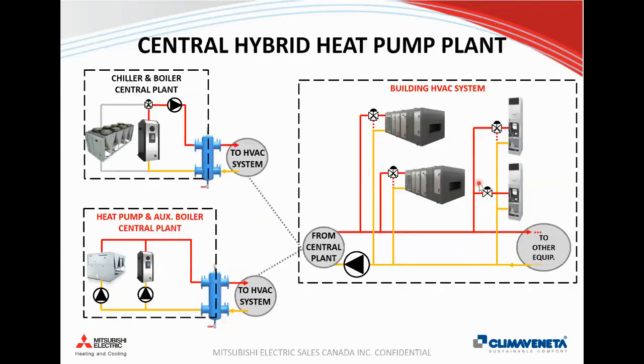So a typical two-pipe changeover system. The typical example I always default to is typical condos. In a past life, I spent a lot of time working for a vertical stack fan coil manufacturer, so I'm familiar with these systems. But a two-pipe changeover system is a system where we'll typically have a heating boiler that we'll use in the wintertime, and we'll shut that off usually May 2-4 long weekend, and then we'll turn on our chiller and start cooling our building.